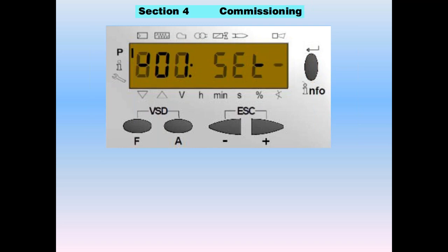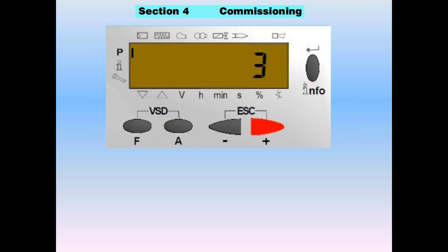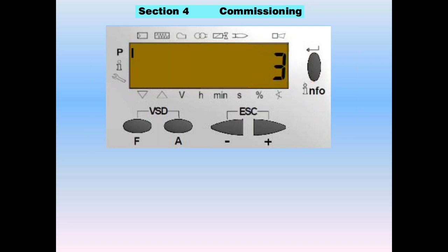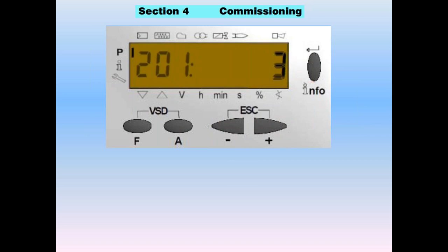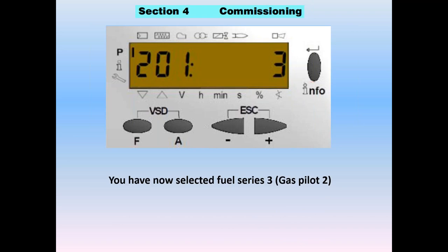From the 800 set, the first thing you'll be prompted for is parameter 201, which has no value yet. 201 is your fuel train. Enter 201, get your dashes, then push plus or minus to dial up the fuel train number you want. Today we're doing fuel train number three — gas pilot number two for the U.S. Once you enter the three and hit enter, the number three will slide to the right as a value. Press escape, and you can review that parameter 201 is set to value three for the GP2 gas train. You have now selected fuel series three.